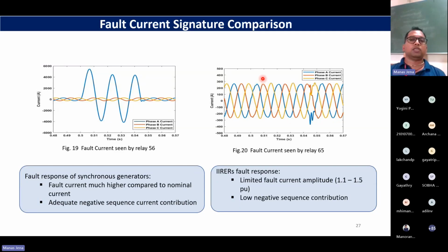So, if you are using an overcurrent relay and you have used some pickup value, okay, say the pickup value is 2000 amps, and if the current is more than that you trip, then from the other side you are completely blind, okay. Because why is it happening? The inverter's fault current is limited to 1.1 to 1.5 per unit theoretically, and then you don't expect such high fault currents, right?